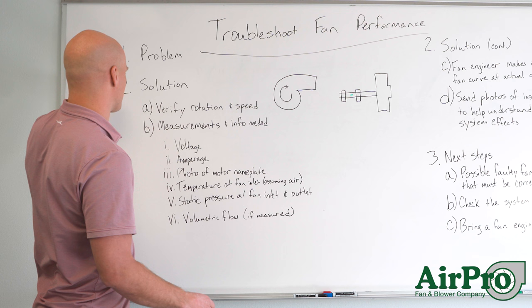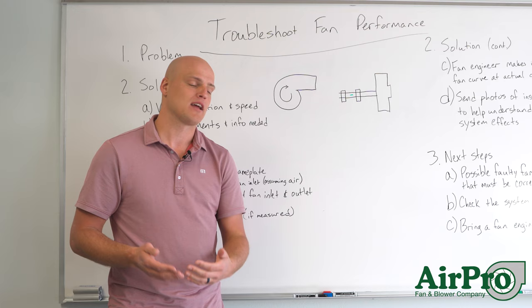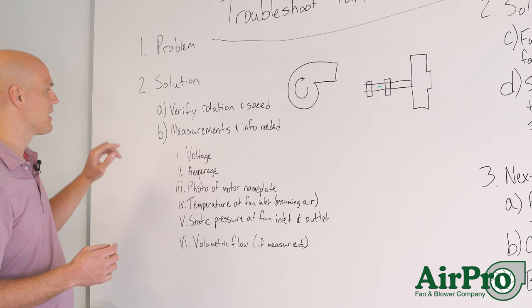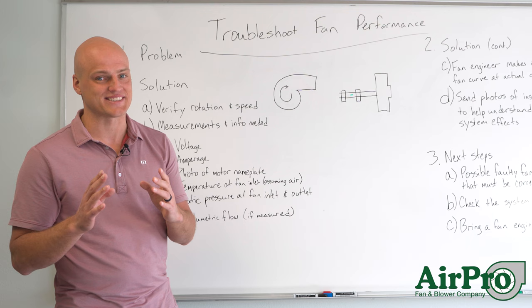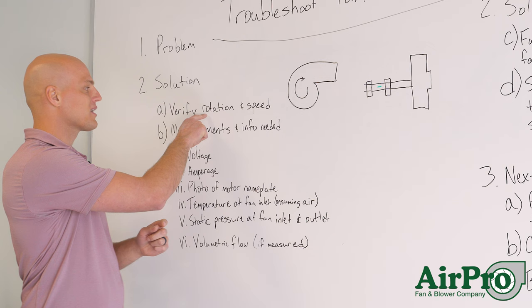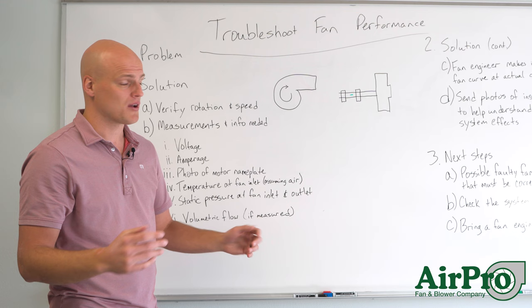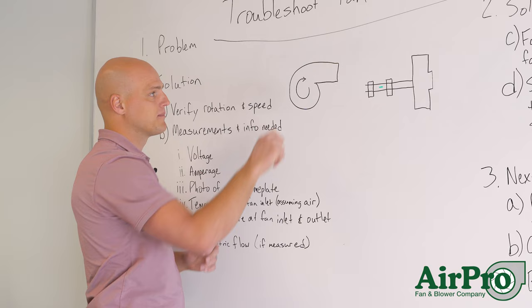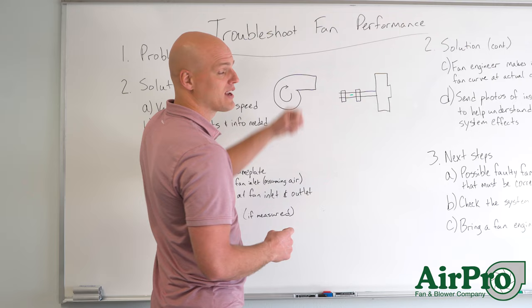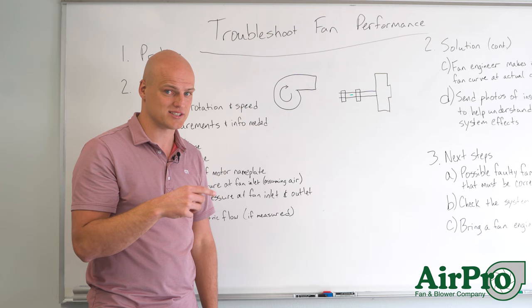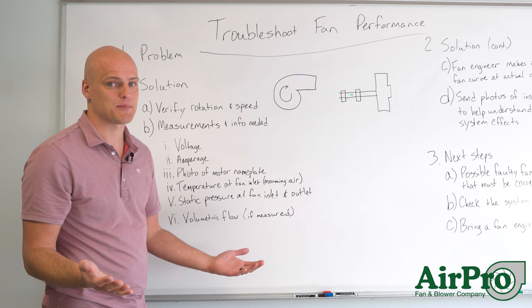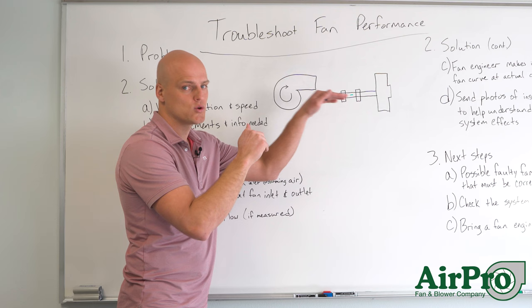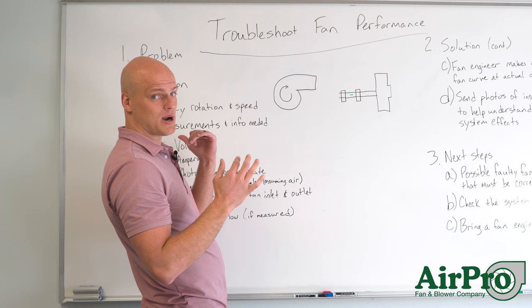We're going to look at number two: what is the solution? First, we're going to ask you to verify a couple of things that may seem very basic, but you'll be surprised at how many issues this catches. We're going to ask you to verify rotation and speed. In a centrifugal fan, you've got an inlet and an outlet. The outlet always indicates how your wheel needs to be spinning — it needs to spin in a way that sends the gas out the outlet. A centrifugal fan will always move air from inlet to outlet even if it's spinning backwards, so just reverse the rotation and you might fix your issue.